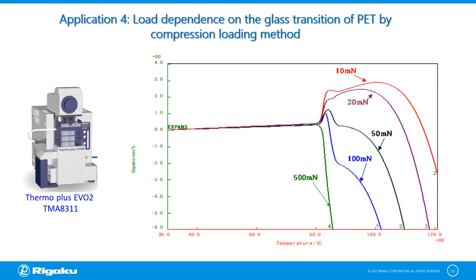This application demonstrates the load dependence on the glass transition of PET by compression loading method. PET material was measured under several load conditions of 10, 20, 50, 100, and 500 millinewtons. The sample presents an expansion curve with a slope change at 80 degrees centigrade due to glass transition, followed by a shrinkage curve due to softening, and these thermal behaviors show load dependence. The larger the load, the less likely we can observe expansion during glass transition, because the detection rod with a larger load will immediately crush the sample. For polymer samples, smaller loads like 10 to 50 millinewtons are ideal; for metals and ceramics, a larger load is recommended.